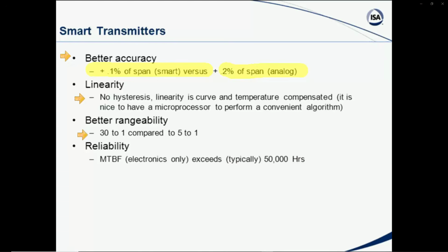Now, rangeability is a term that we didn't cover a little earlier, but it's typically defined as the ratio of the maximum upper limit that we can measure with the stated accuracy to the minimum that we can still maintain that same degree of accuracy. So perhaps in some of our older devices, this was more like 3 or 4 or 5 to 1, and now in some cases you get a much higher rangeability between the upper and lower limits of your spans.